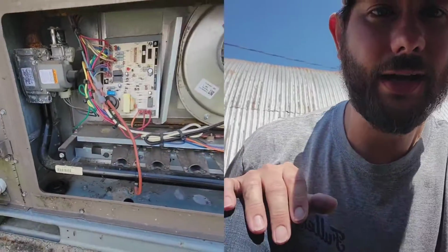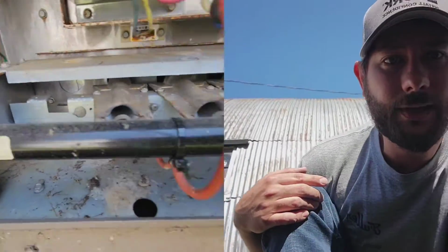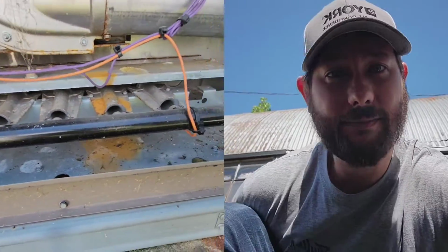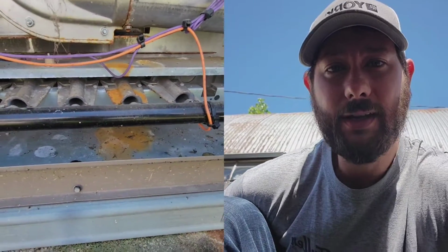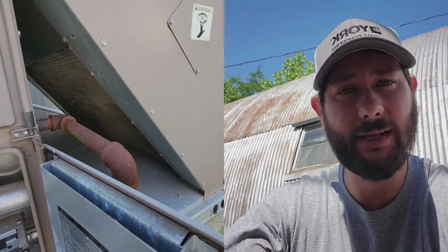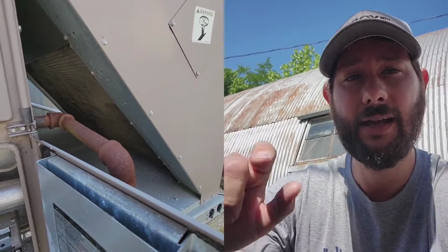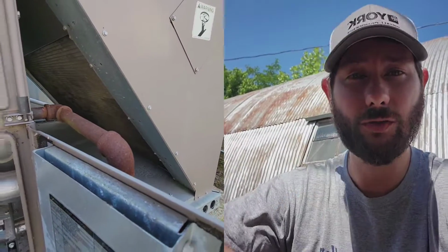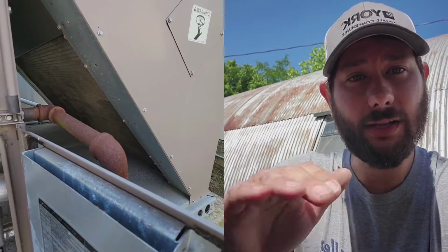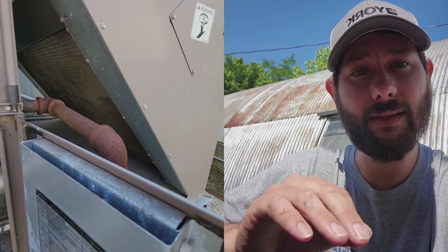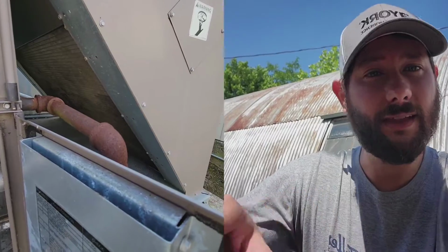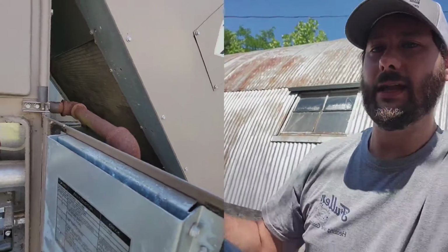So this right here is your burners, and your burners need to be maintained. You need to have some type of cleaning process, whether it's a steel brush, whether it's sandpaper, so that you can clean those burners and make sure that track is clean, because that's the flame carryover track. If you don't have clean burners and they're rusty, then they won't carry the flame over. So that's something that can happen.